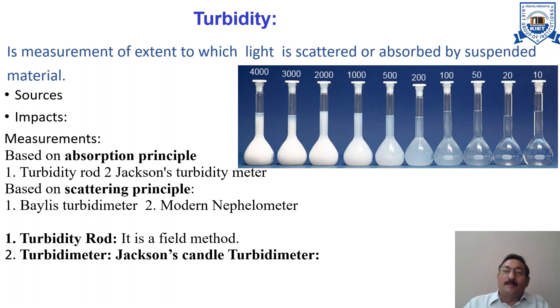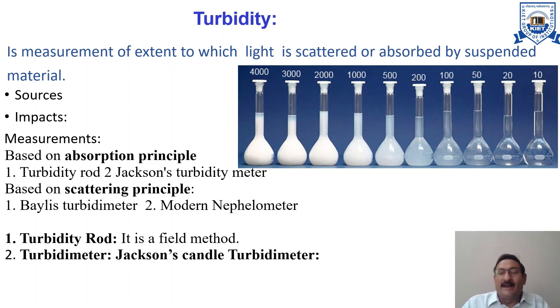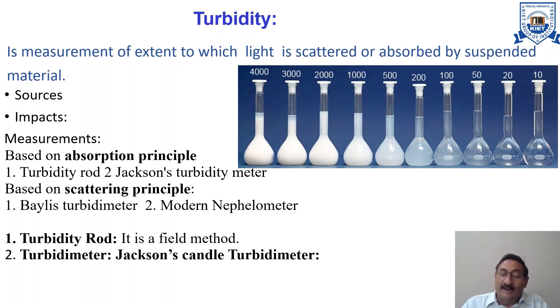The next parameter is turbidity. Turbidity is a measure of the extent to which light is either absorbed or scattered by suspended material in water. Since scattering and absorption are influenced by both the size and surface characteristics of suspended material, turbidity is not a direct quantitative measurement of suspended solids.